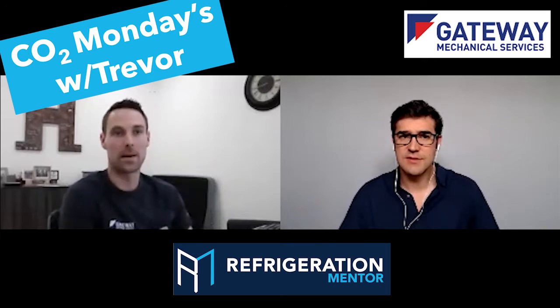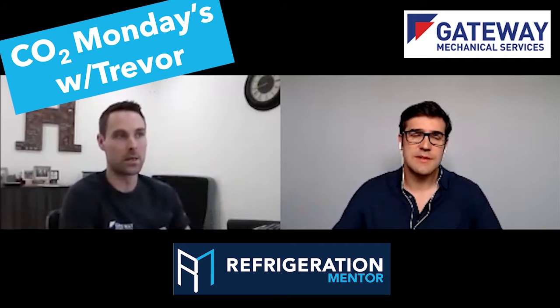I love that. And that's what I do when I go into a new store or a new piece of equipment. You really want to understand that. And that last one, you said the last one was System LMP, I believe, and they have a reverse gas defrost. Is that correct? Yeah, the LMP rack, it's a traditional hot gas, reverse flow.